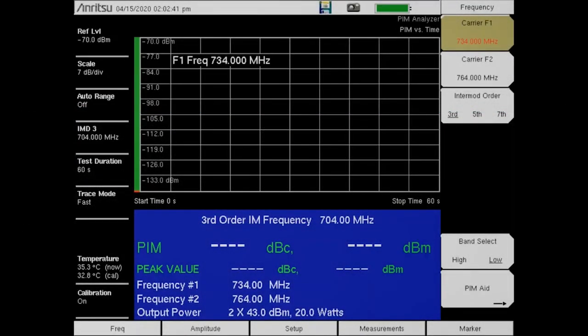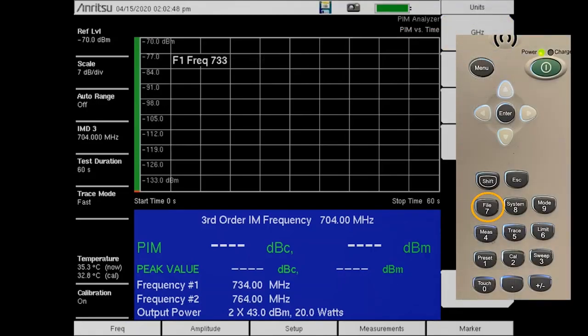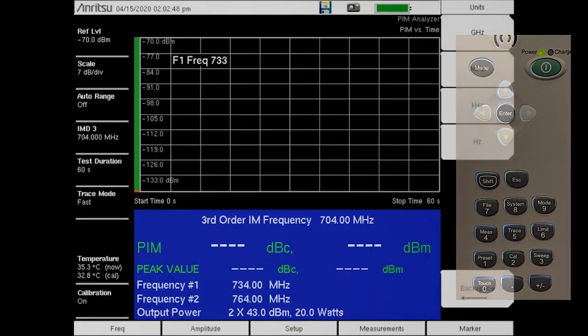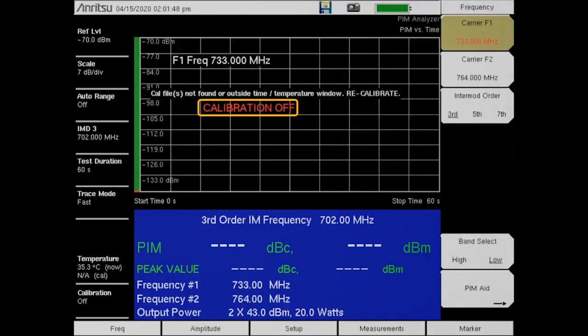We will start by entering a custom frequency for frequency 1 of 733 MHz. Press the Freq button, followed by the carrier F1 button. From the keypad, enter 733 and then press the megahertz key. Take notice of the calibration off indicator on the screen.